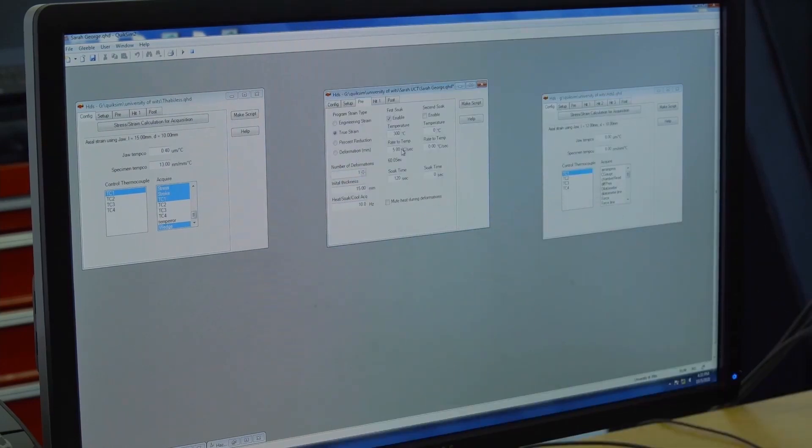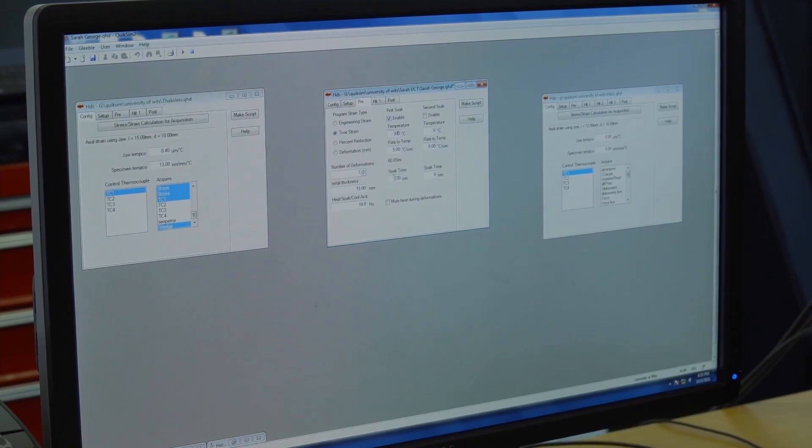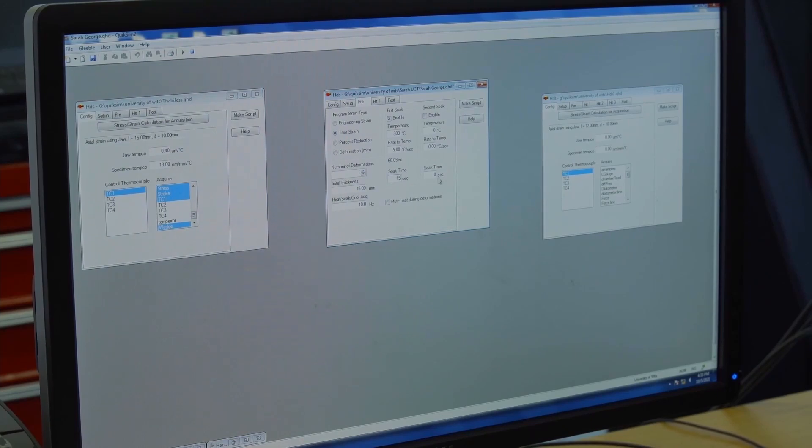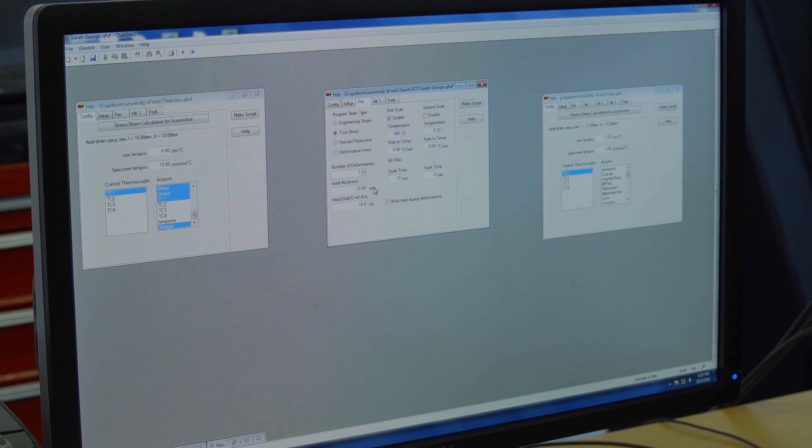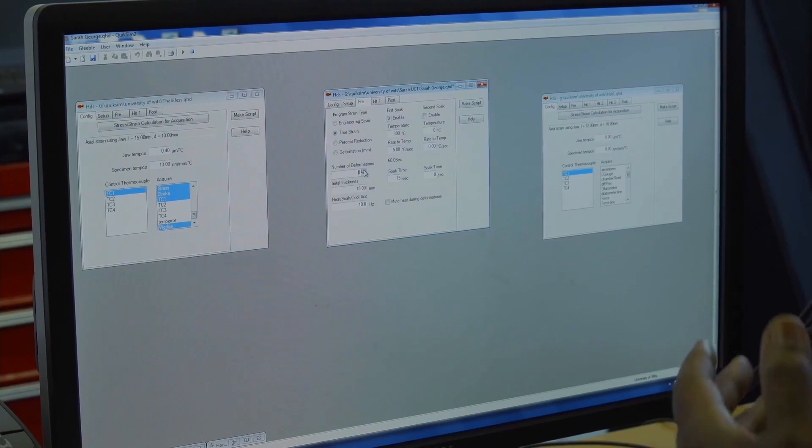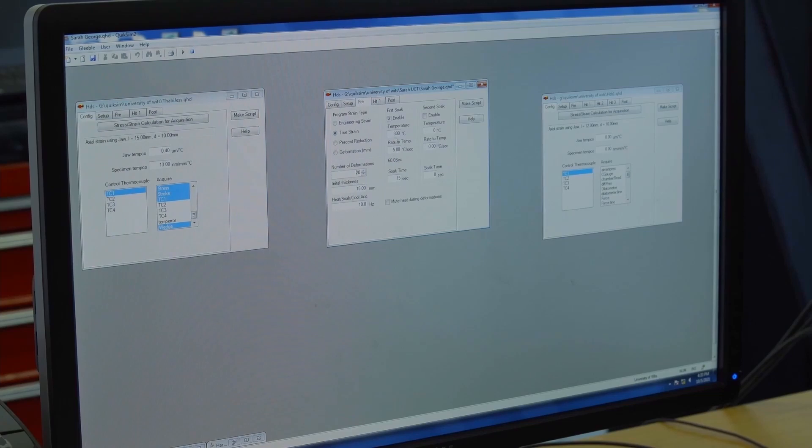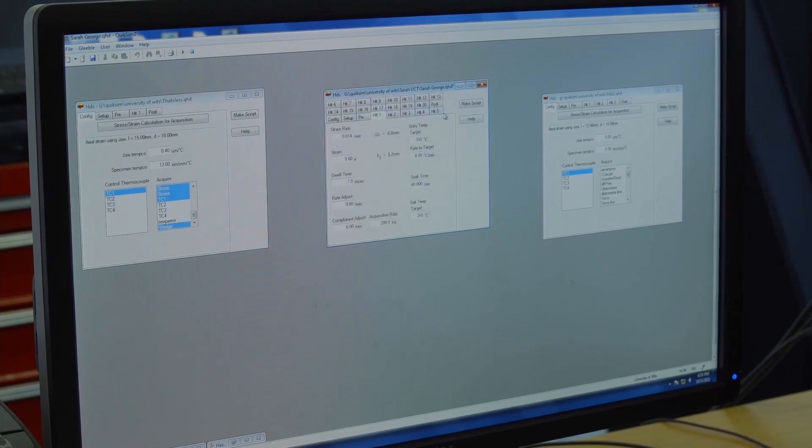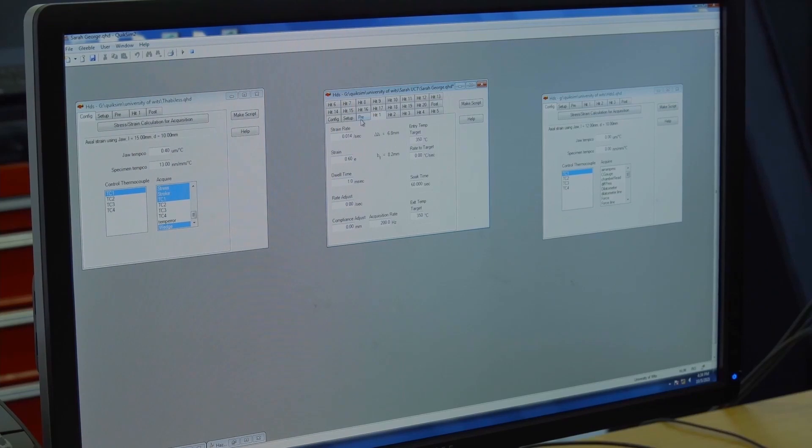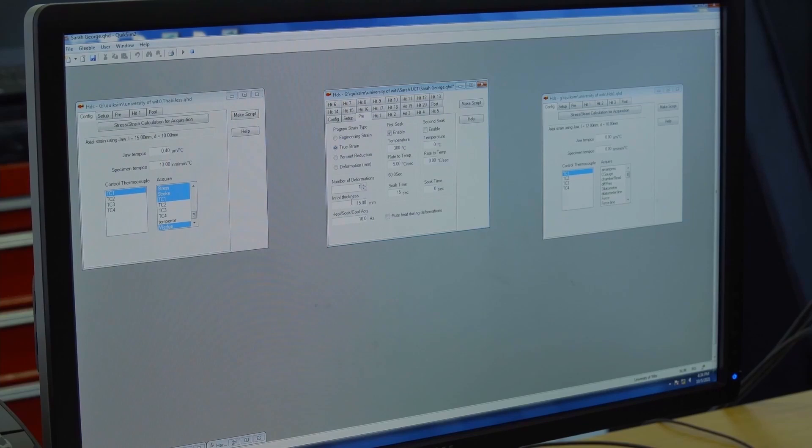Here, the rate at which the Gleeble heats the sample to attain this temperature is 5 degrees Celsius per second. That is the recommended heating rate for the ISO-Q anvils that you have on the Gleeble. We want to hold for 30 seconds. If you are simulating rolling operation, you may want to increase this to many heats. You can have up to 20 heats here. We really don't need that because it's just forging that we are simulating, and forging is just one stamp.